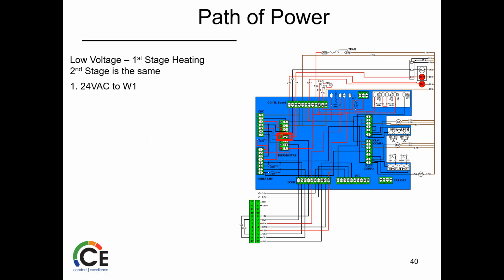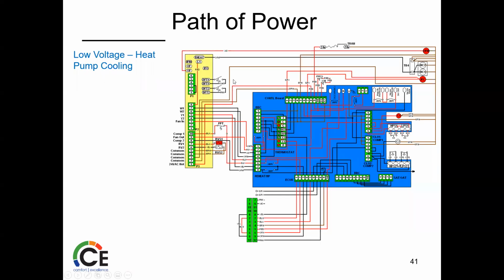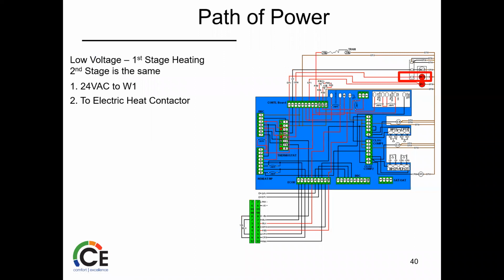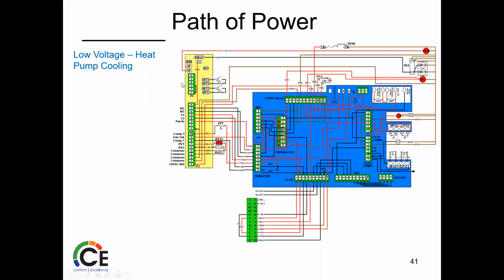Now, if we're talking heating, we're going to get that W1 call. Now, this is obviously a heat pump system, so it's going to look for that electric heat contactor. It's going to energize that for W1. And then obviously we're going to get the same thing. We're going to get the fan, we're going to get W1, and then off we go. If it's a heat pump, we're going to get that W1 call down through the economizer again, same exact path, looking for jumper 5 because we're talking about W1 or Y1.